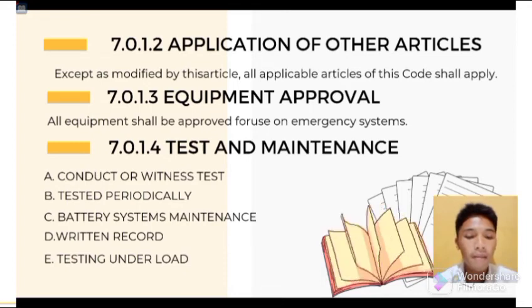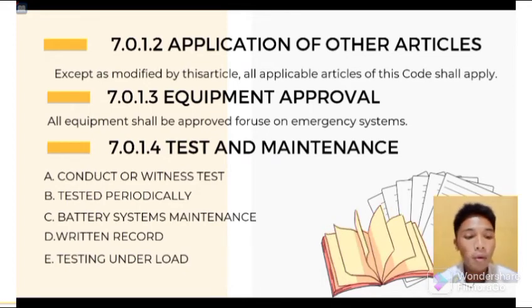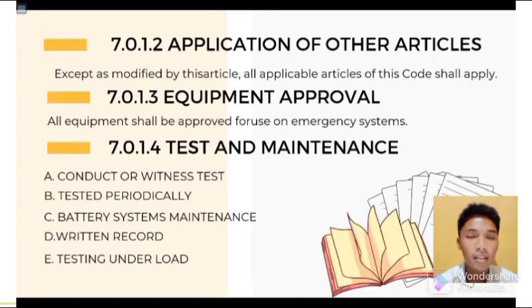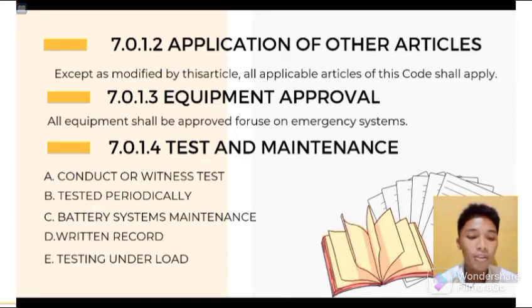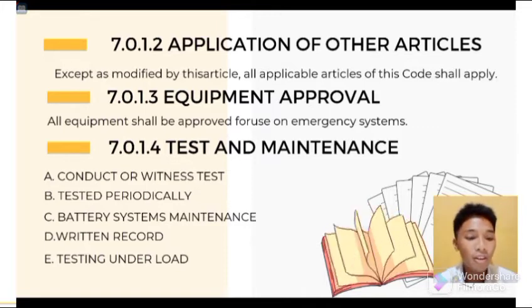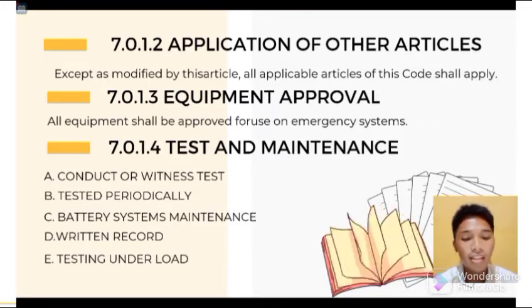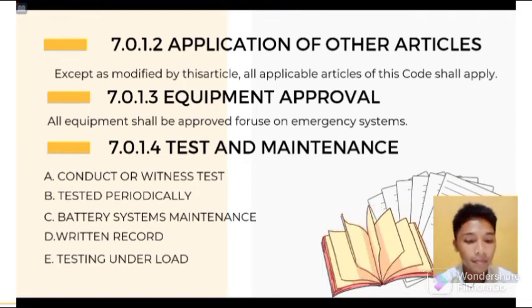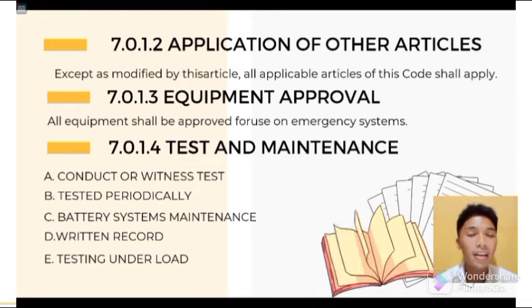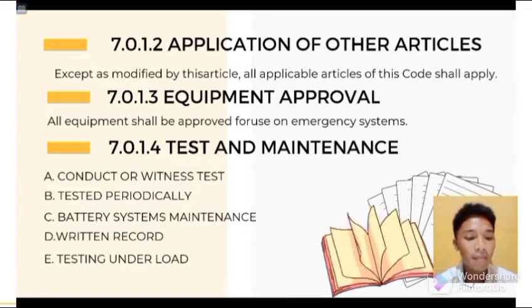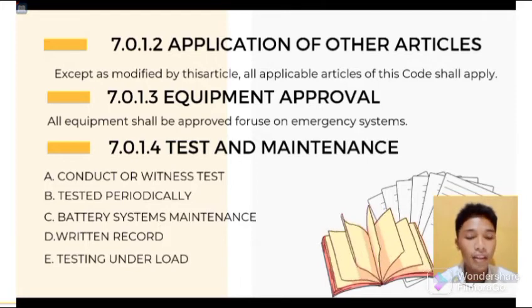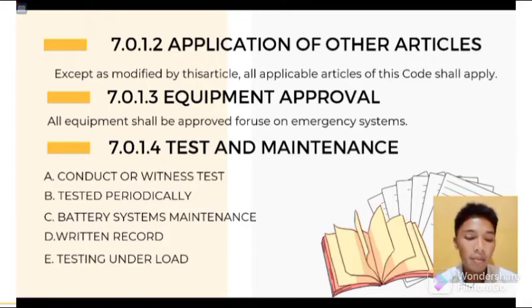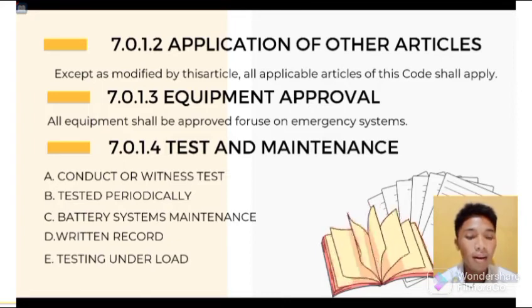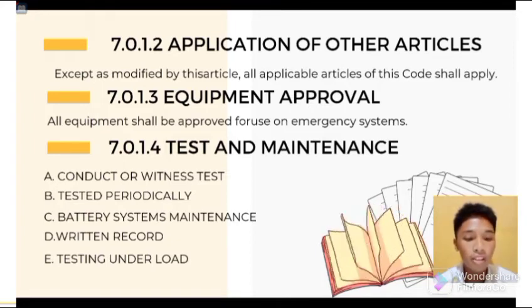C. Battery system maintenance. Where battery systems or unit equipment are involved, including batteries used for starting, control, or ignition in auxiliary engines, the authority having jurisdiction shall require periodic maintenance. Letter D, written record. A written record shall be kept of such tests and maintenance. Letter E, testing under load. Means for testing all emergency lighting and power systems during maximum anticipated load conditions shall be provided.